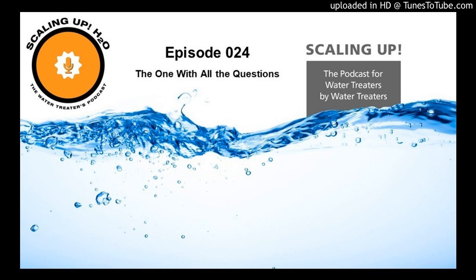Well, you can't get it out of the system, but you can figure out how much is an issue. And normally it says, iron might be 3 parts per million or above. So if it's that and you've got more than that, you can dilute the sample. And from that sample, you're now testing less of the actual water that's creating the issue, and you can run your test hopefully without any problems.